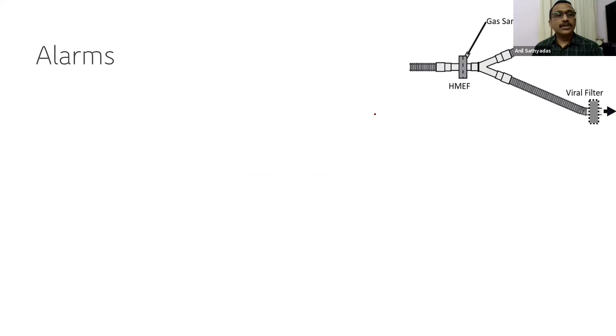And then you have to switch on all the alarms that will tell you about problems when you ventilate such patients. One of the most important alarms, I think, is the exhaled tidal volume. If you ask the ventilator to give 400 ml to the patient at the inspiratory limb and 100 ml leaks out, the patient gets only 300 ml. Nobody will know the patient got only 300 ml. So you have to measure what is coming out of the lung by keeping a sensor in the ventilator. That's called the exhaled tidal volume. The difference between the inspired and the exhaled should be less than 50 ml.